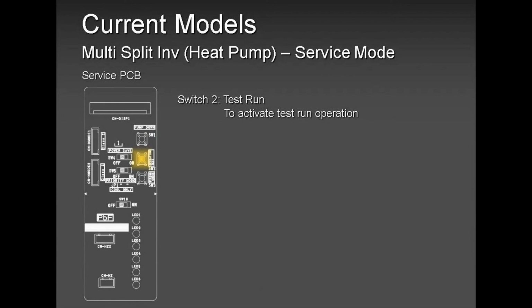The homeowner comes, and whatever job you want to do, relocate the indoor unit, reduce an indoor unit, or add an indoor unit, you can do that. Pump down for 15 minutes. In most cases, it is assumed that the pump down will take 15 minutes. I have done a few pump downs and I've never gone past 15 minutes. It was always 5, 6, 7. It all depends on how much refrigerant was in the system.